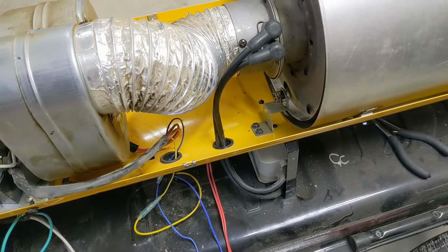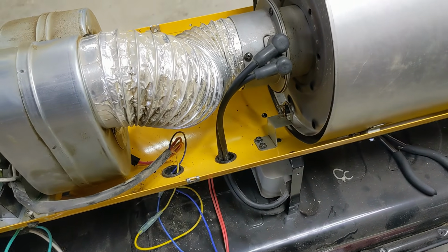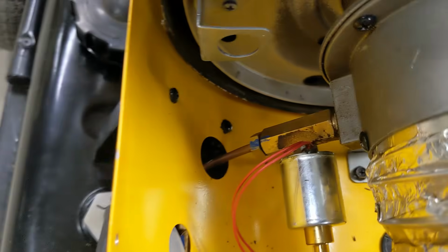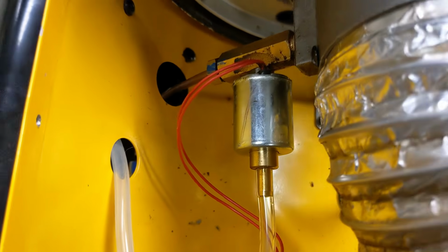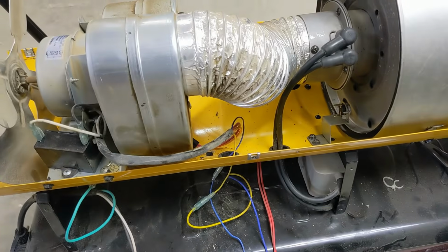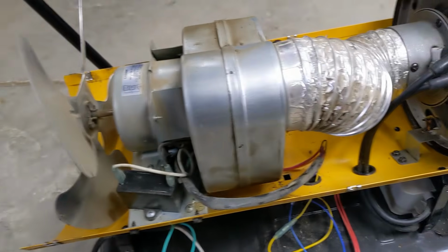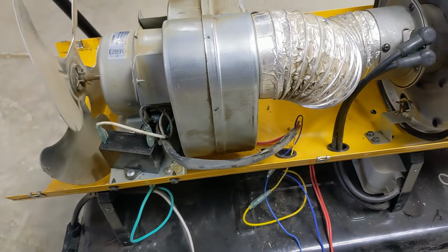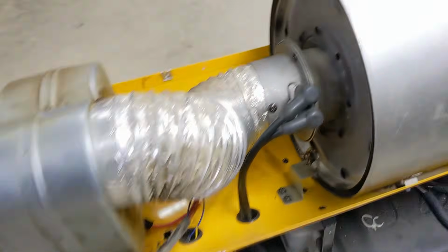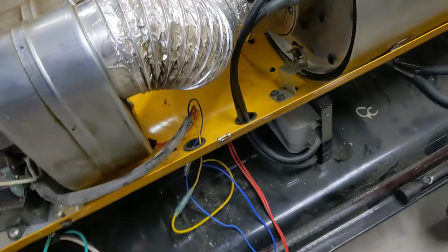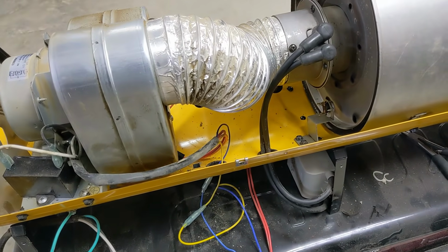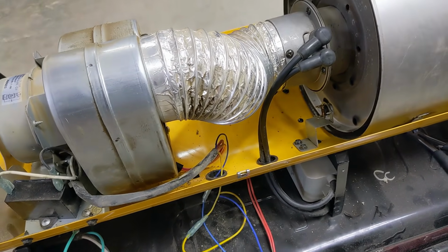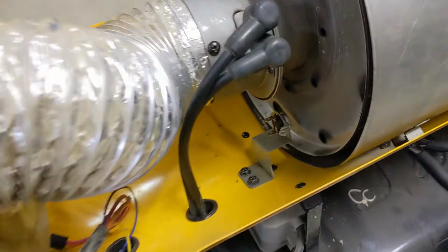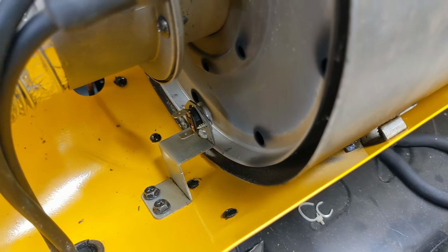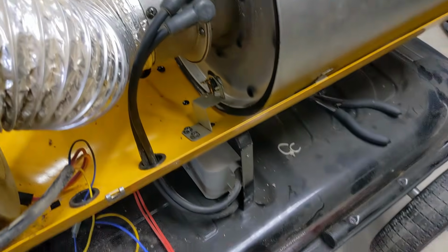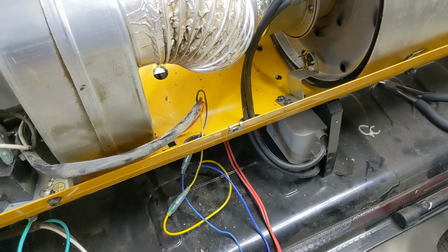Well, it wouldn't be shooting fuel out if the pump didn't work. So obviously the pump works. Obviously the fuel solenoid over there works, or else it wouldn't run because it wouldn't open to let the fuel in. The fan runs just fine, it's strong. Well, there's nothing left. I took out the igniter, set the gap on the igniter. That's fine, checked out. So that's it. The only 2 sensors it has are that thermal overload and the photocell. That's it.